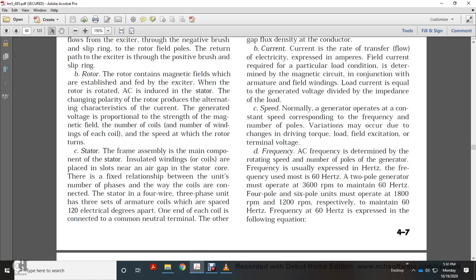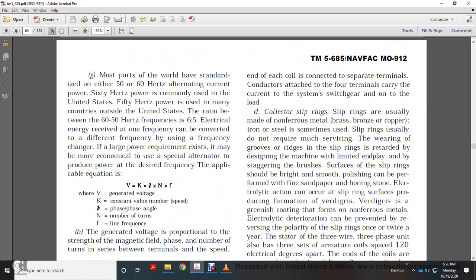Next, the stator. The frame assembly is the main component of the stator, with insulated windings placed in slots along the air gap of the stator, in a fixed relationship. The number of phases determines the coil layout. In the four-wire, three-phase unit, there are three sets of armature coils spaced 120 electrical degrees apart. One end of each is connected to the common neutral terminal. The other end of each coil connects to a separate terminal, with the conductors attached to the four terminals, carrying current through the switchgear to the load.